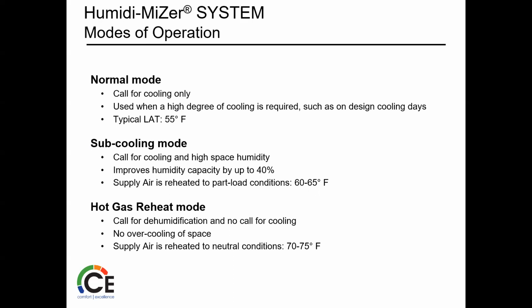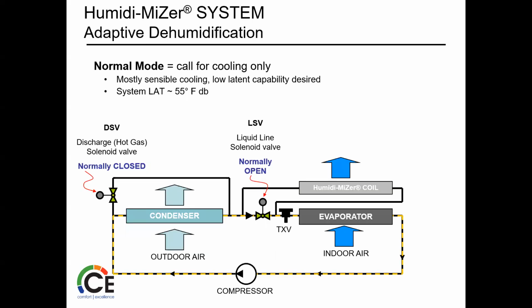So normal mode, call for cooling, is used when a high degree of cooling is required, like design cooling days and low ambient conditions. When a Humidi-MiZer, I could have thought of a different word, is combined with a two-circuit unit, again the 03 to 28 is the size, it's not an RTU. Depending on the space conditions, one circuit could be in hot gas reheat mode while the other is in subcooling mode, often referred to as the fourth mode of operation. So this gives you a lot more options than just a basic series flow or two-stage system. So we're changing things up, we're metering it, and as they slowly go through, they're trying to improve.